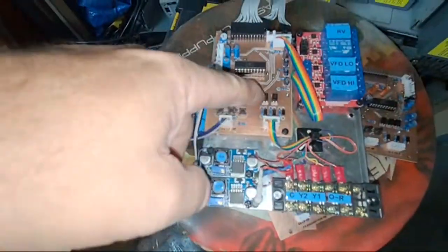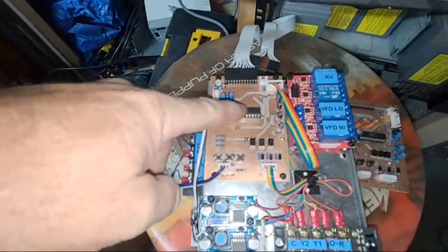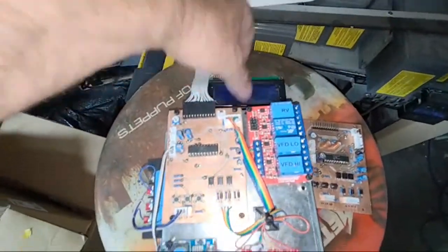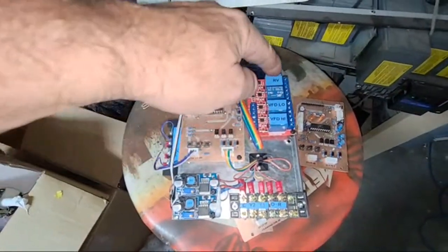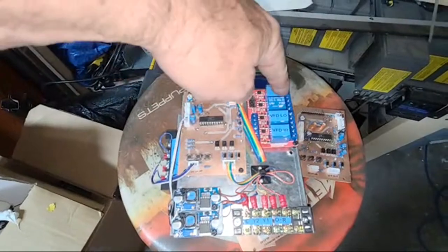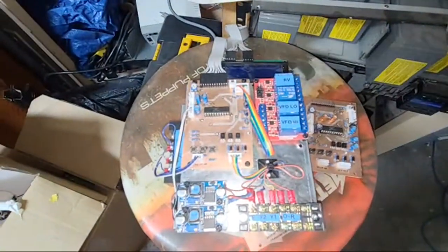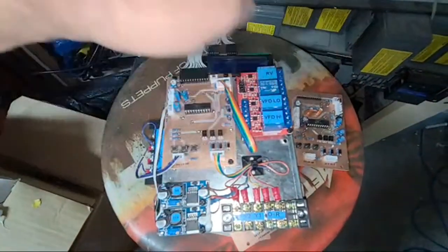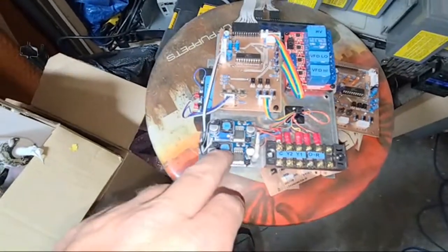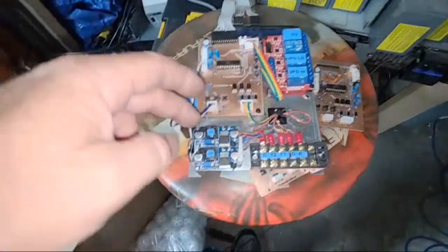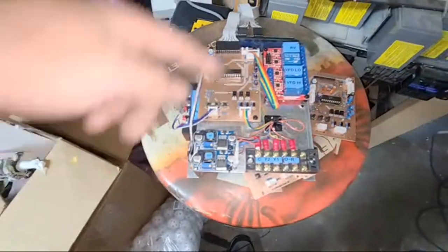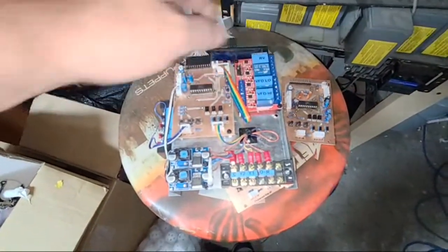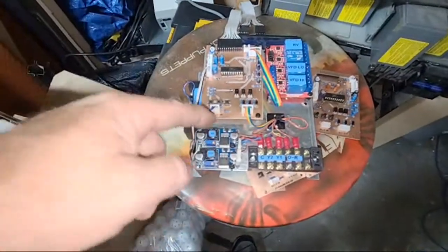24 volt interface, optical isolators, my microprocessor, my LCD, my reversing valve relay, because it's a high voltage reversing valve in mini splits, and then high and low for my VFD command. It wasn't too overly built, other than I had two power supplies, 12 volts for that, 5 for that. If I could have found one of these boards with 5 volt coils, I could omit one of these power supplies and only use the 5 volt.